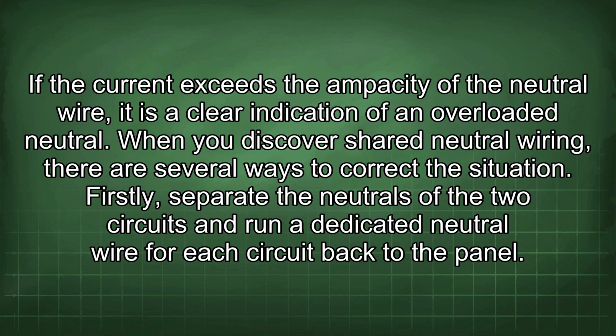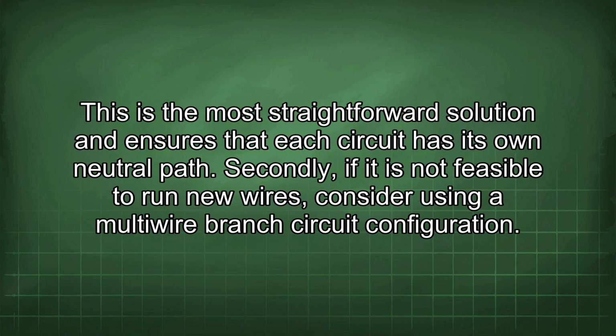When you discover shared neutral wiring, there are several ways to correct the situation. Firstly, separate the neutrals of the two circuits and run a dedicated neutral wire for each circuit back to the panel. This is the most straightforward solution and ensures that each circuit has its own neutral path.